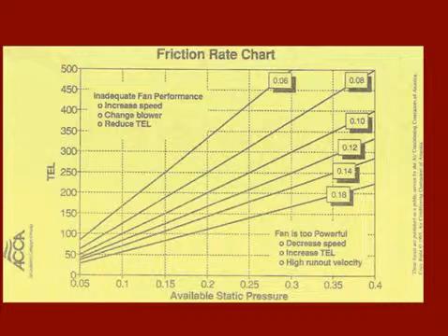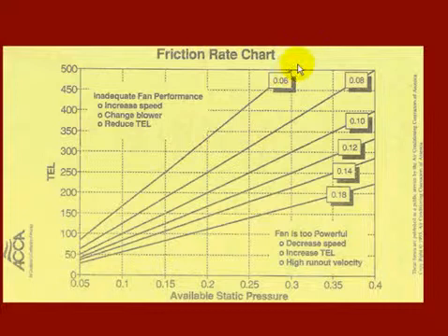This is what I think has a lot to do with, maybe not directly, but this concept of how a duct system should be designed. If you read ACCA Manual D, or if you ask an ASHRAE engineer, what friction rate should a residential duct system be designed at, and we're going to talk about that in a minute, he will say somewhere between 0.06 and 0.18 inches of water column per 100 feet of duct, because it's a rate.